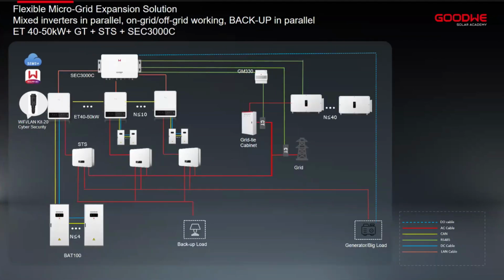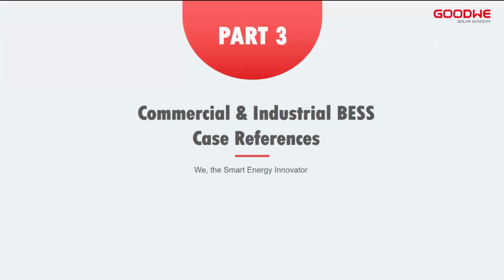Similarly, if you're now doing a microgrid or a mini grid, the SEC3000C can control up to 10 ET series. The battery side, as I mentioned before, you can do 4 pieces with the BAT outdoor, 6 pieces with the BAT indoor. And on the on-grid side, you connect the GT series, up to 40 pieces of the GT series. Now, this is able to keep you running in a microgrid scenario. So this is another typical scenario that you can achieve.